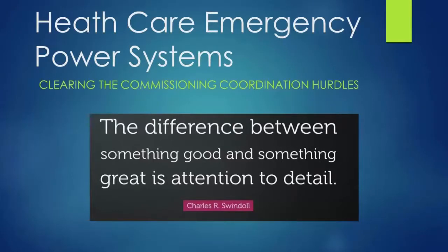One is the emergency power supply system test, and the other is the black site test. In the black site test, we do a coordinated and controlled loss of normal power to the whole facility. We want to see what happens to the facility during that loss of power. We're not necessarily testing the emergency power supply system, but a black site test, like you indicated, is going to affect all of your mechanical equipment.